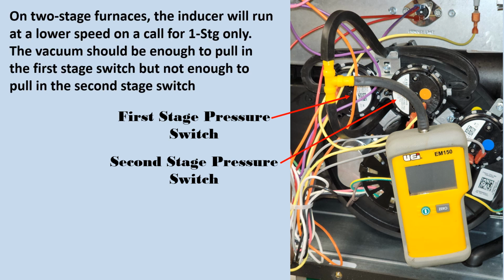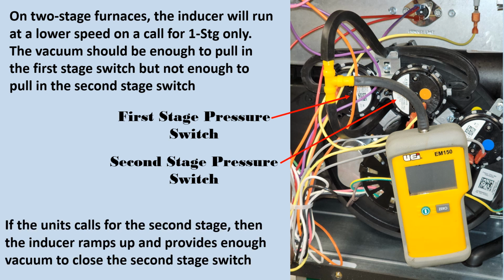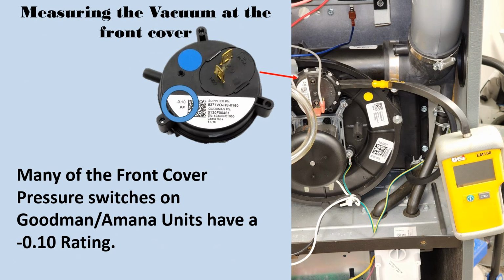On 2-stage furnaces, the inducer will run at a lower speed on a call for first stage only. The vacuum could be enough to pull in the first stage switch, but not enough to pull in the second stage switch. If the unit calls for the second stage, then the inducer ramps up and provides enough vacuum to close the second stage switch.